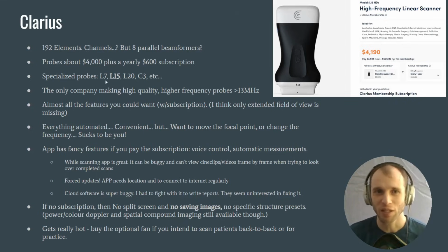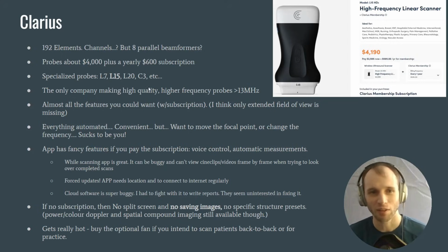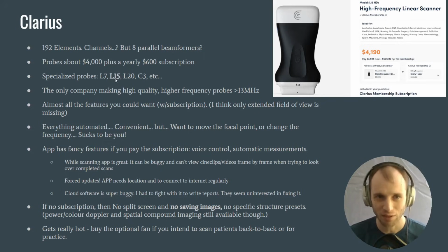They make very specialized probes. They have an L7, an L15, an L20, a C3, etc. The L7 would be a general purpose linear probe, about 4 centimeters wide, a maximum depth of 11 centimeters. The L15 is a musculoskeletal focused probe. It has a width of 5 centimeters and a maximum depth of 7 centimeters. The L20 is a very small probe. I think the footprint is just 3 centimeters, something like that, but has, of course, a very high frequency. So very, very shallow structures, very high resolution, and then they have a curvilinear, and they have a sector probe, and all sorts of other probes. But for our purposes, you'd probably be interested in one of these 3, and then of course if you wanted to add on a curvilinear for, let's say, the hip, then you'd have to buy the C3. You'd have to buy a whole extra probe.